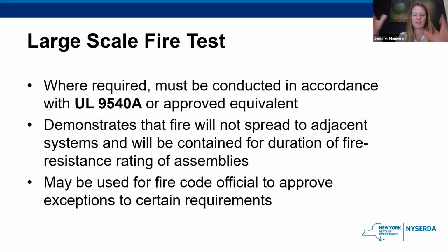And so if during the test, it shows that forcing one chunk of a system to catch on fire does not spread to a system that's adjacent to it, that's great. And the results of this large scale fire test can be used for the code official to approve exceptions to certain requirements in the code. And there are a lot of them, as you'll see in some of the coming slides. There are many code requirements that are like, you shall have at least 3 feet of space between 2 chunks of a system, right? So that there's some separation between them so that if one catches fire, it won't propagate to the one next to it. However, if the large scale fire testing shows that this particular system is safe enough to have, for example, 2 feet apart, the code official can make that exception based on the results of the large scale fire test. That's one example. There are many more.